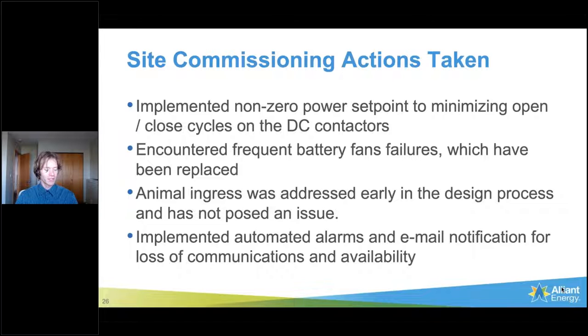There are some limitations that the equipment has which really weren't known in advance, and that's part of the reason these are pilot projects. One of them was that the DC contactors would open and close really frequently when there's a zero set point for the battery. In order to really minimize that, we initiated a more regular charge-discharge cycle that'll keep the DC contactors from unnecessary cycling. Lifetime on those DC contactors, at least for this installation, has been highlighted as a major issue.